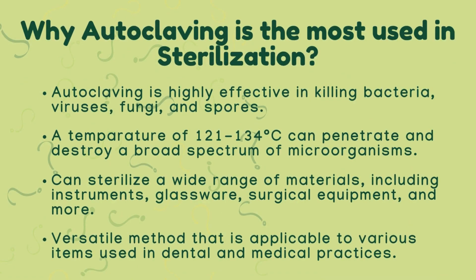Autoclave is the most used in sterilization. So, why is it most used in sterilization? Autoclaving is highly effective in killing bacteria, viruses, fungi, and spores. The combination of high temperature, typically 121 to 134 degrees Celsius, and pressure penetrates and destroys a broad spectrum of microorganisms. Autoclaves can sterilize a wide range of materials including instruments, glassware, surgical equipment, and more. It is a versatile method applicable to various items used in dental and medical practices.